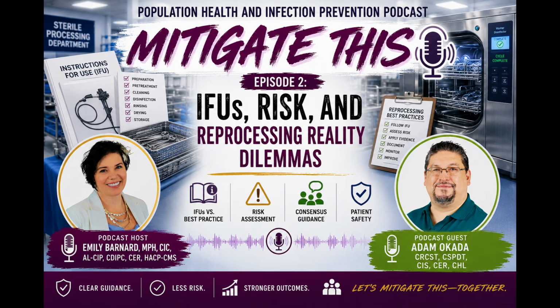And then in 1990, there was the Safe Medical Device Act, and that included more post-market surveillance of devices. So they required facilities to report adverse events. This is like hospitals, nursing homes, anything where there were medical procedures going on, they were required to now report. Before that, it was just manufacturers. And you can imagine that manufacturers were not always the most honest and upfront about issues with their own devices.